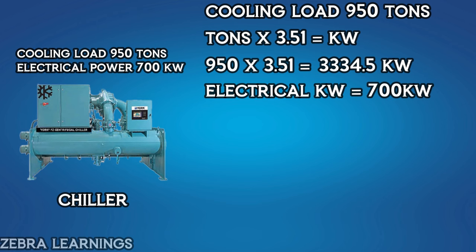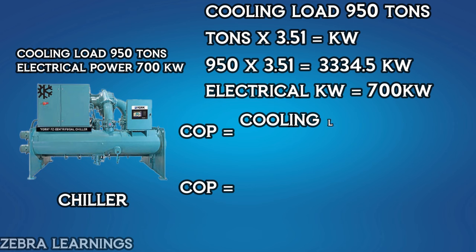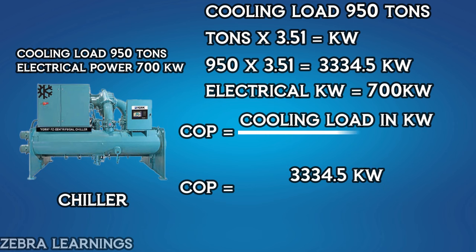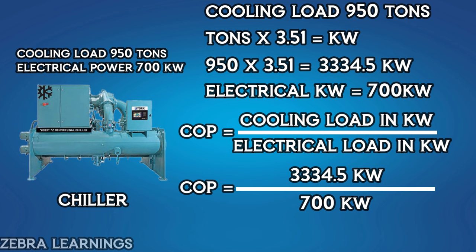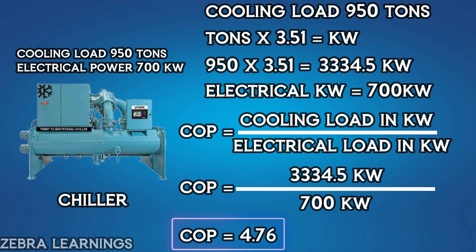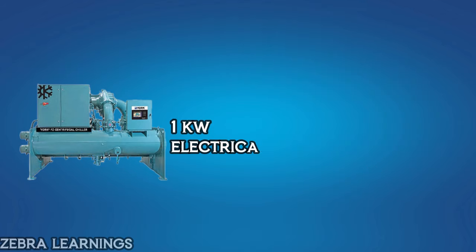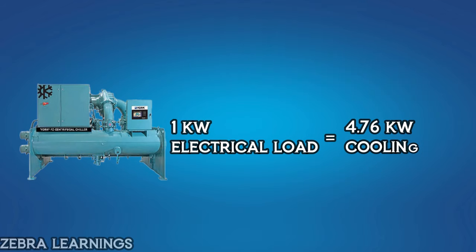Now we can use these values in the formula. COP equals cooling load 3334.5 kilowatts divided by electric load 700 kilowatts, which equals 4.76. The chiller's efficiency is 4.76. This means that for every 1 kilowatt of electric load, we get 4.76 kilowatts of cooling load.